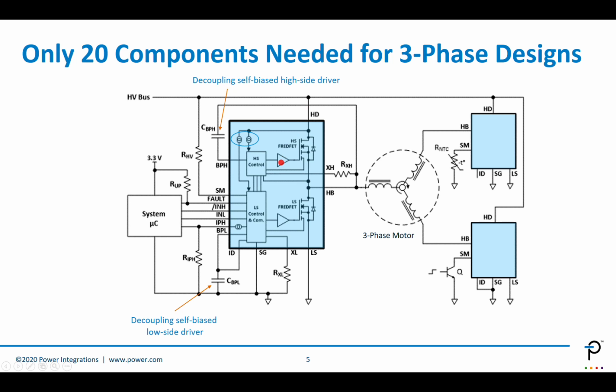BridgeSwitch also has an internal shunt regulator which allows supplying it externally in case self-supply is not suitable. The device monitors currents through the FREDFET independent from the microcontroller or any external circuitry or the software. The cycle-by-cycle current limit is set with external resistors, here RXH and RXL, and is done independently on the high side and low side. The current limit is adjustable with the maximum value found in the datasheet corresponding to the part number. When the value is exceeded, the respective FREDFET will stop switching. For example, the high side will stop switching, and it will report the fault condition over the diagnostics bus, fault bus, to the microcontroller. And in response to that, the microcontroller can take action, for example, by turning off the complete inverter.